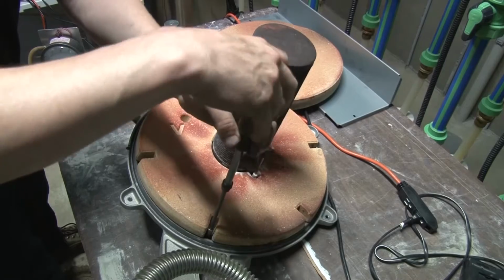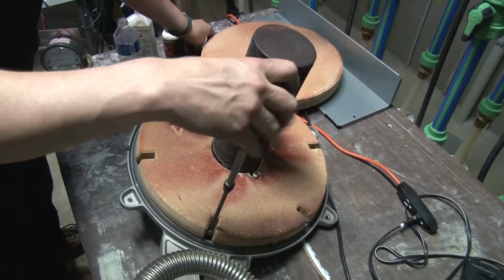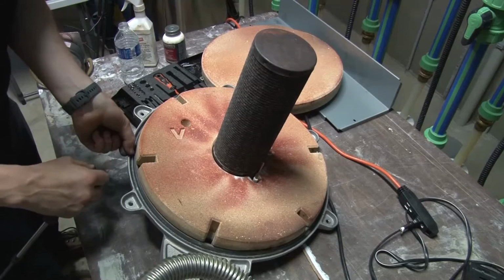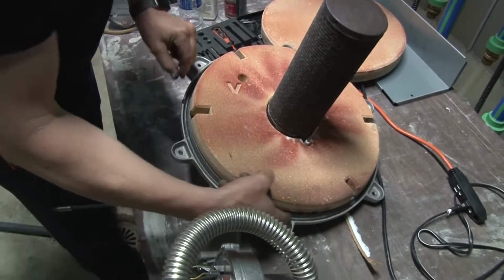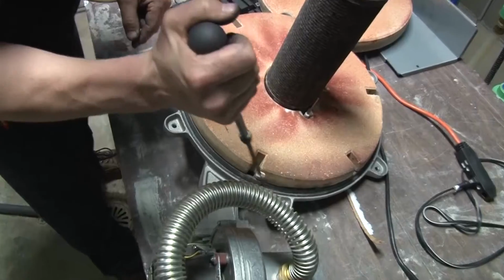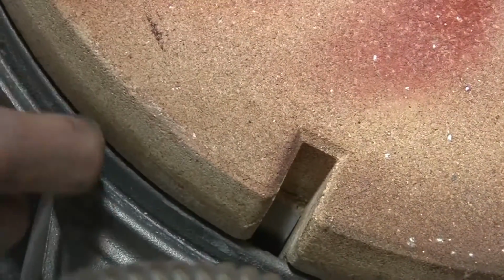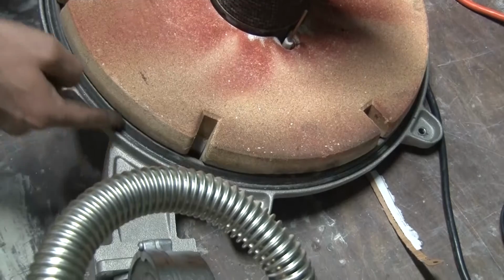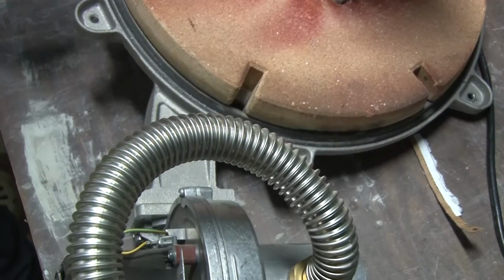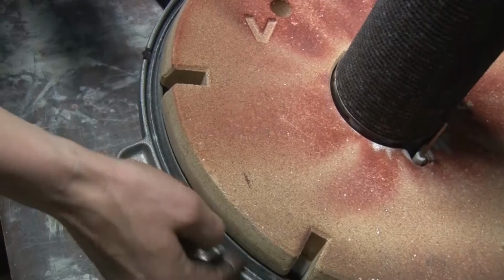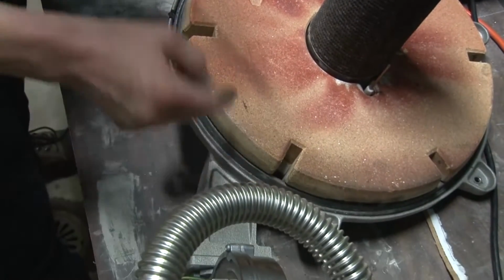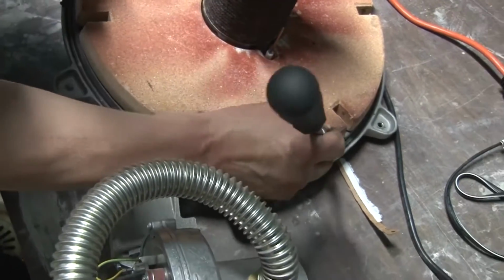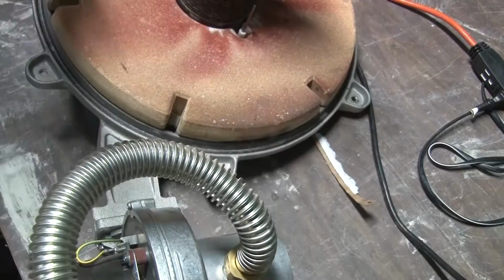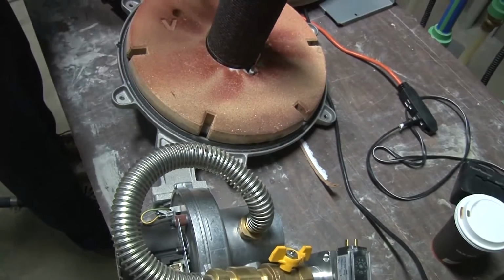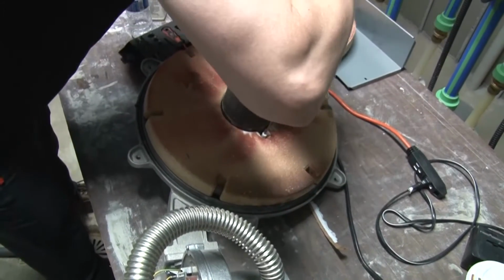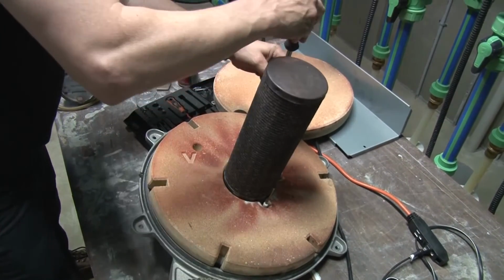An area I want to point out with the burner flange is the burner gasket. There's a gasket that we can see here around the burner. And we're just checking that basically to make sure that that burner gasket's actually still there. Sometimes if the guy hasn't torqued the bolts down correctly, this little burner gasket will basically start to disintegrate, dry out, or crack. We want to make sure it's nice and pliable, right? Make sure that it's going to basically seal up correctly. If that thing fails, it can basically create an issue with your heat exchanger.